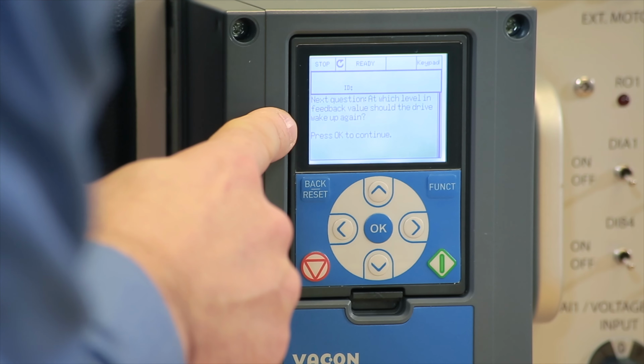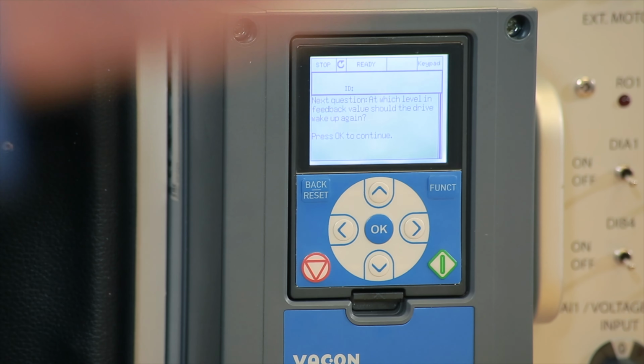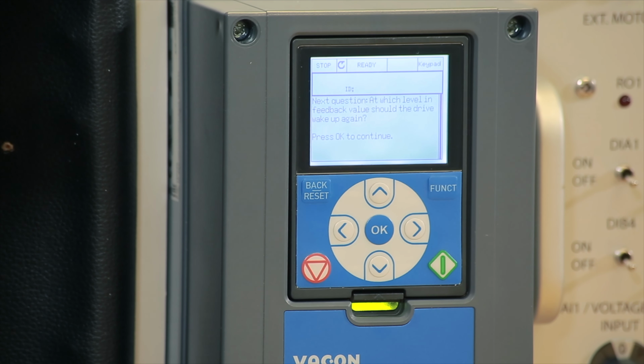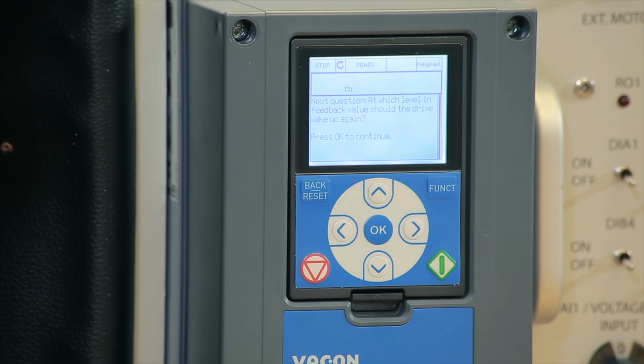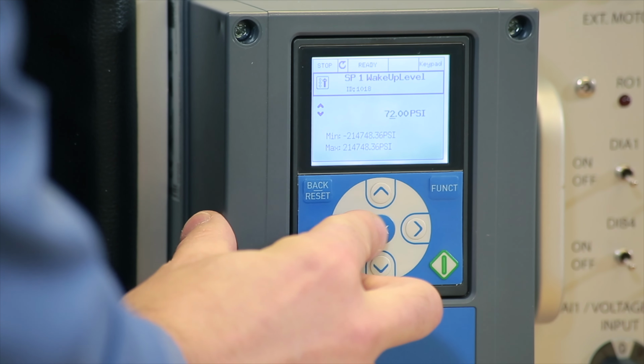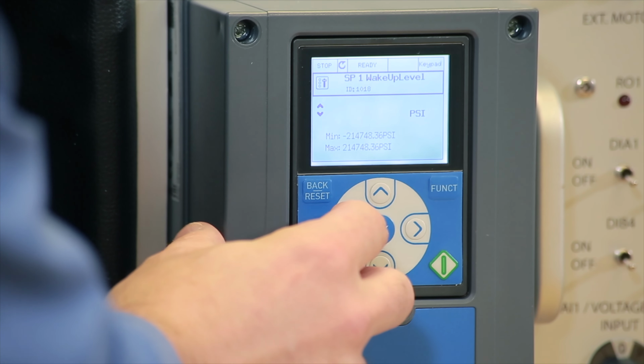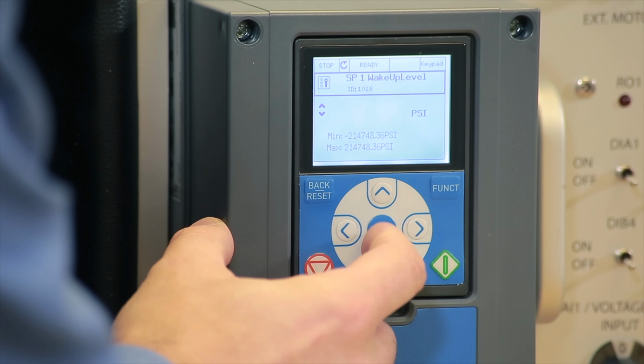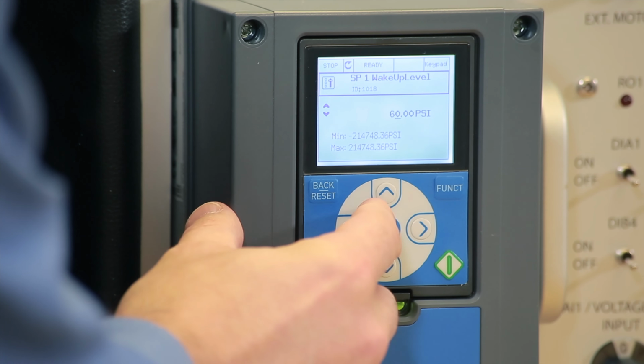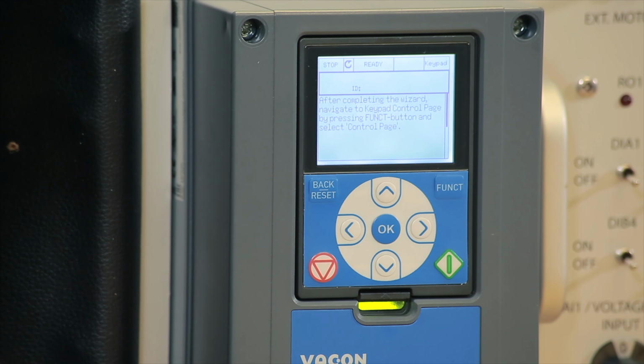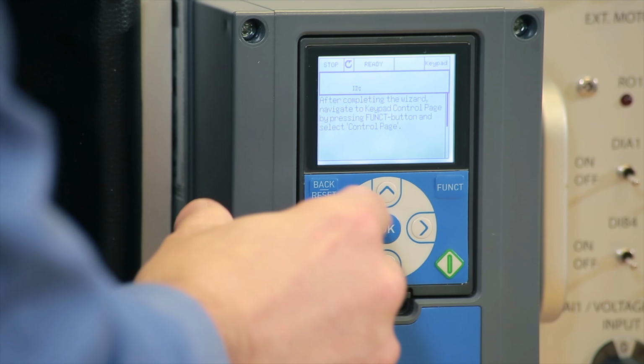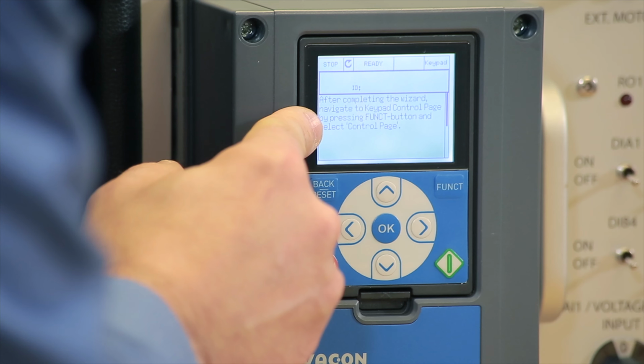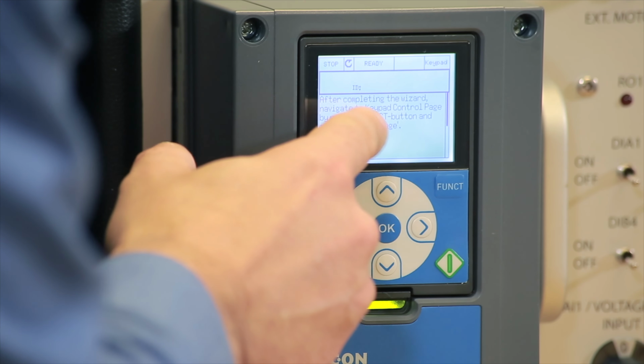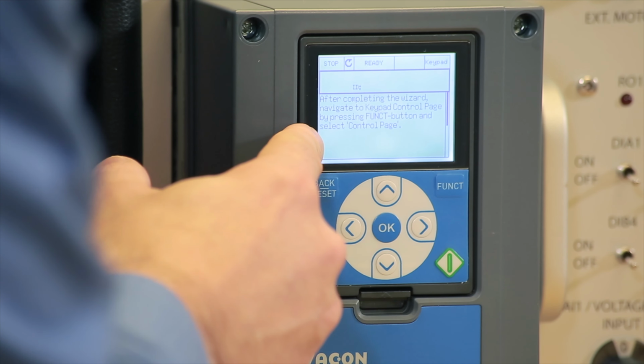So we're going to click OK, and then the drive says, next question, at which level in feedback value should the drive wake up again? So now let's think about this. The drive is asleep because we have achieved over 80 psi. So now when do we want it to wake up? 70 psi, 60 psi, this depends on the application. In our case scenario, the default value is 72, but we can put it to 60 psi. So set point at 80, wake up level at 60 psi. After completing the wizard, navigate to the keypad control page by pressing the function button, which is this button here, and select control page.